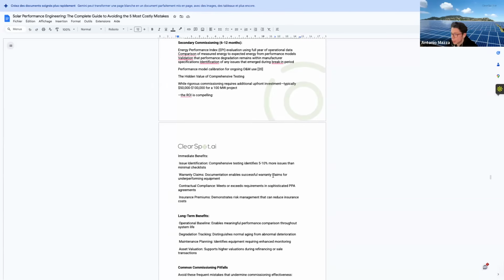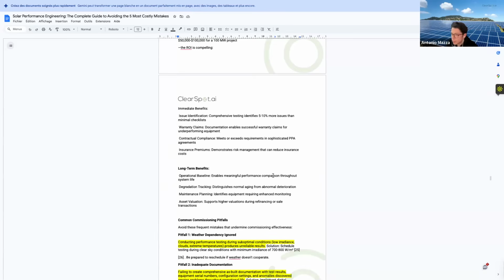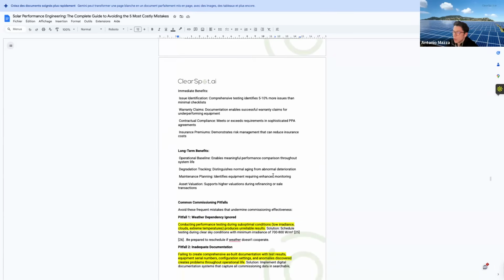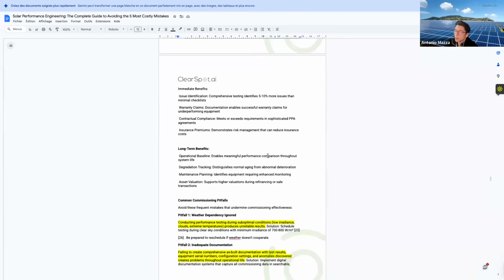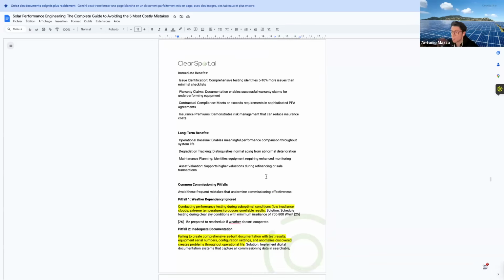Long-term benefits: we know the operational baseline, degradation tracking, maintenance planning, asset valuation. Common commissioning pitfalls. Number one, weather dependency ignored: conducting performance testing during suboptimal conditions, low irradiance, cloud, extreme temperature, produces unreliable results. Inadequate documentation: failing to create comprehensive as-built documentation with test results, equipment serial numbers, configuration settings, and anomalies discovered creates problems throughout the operational life.